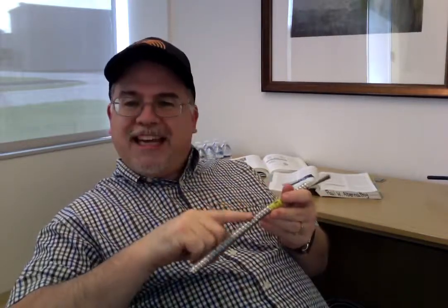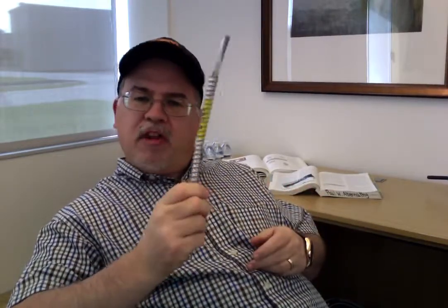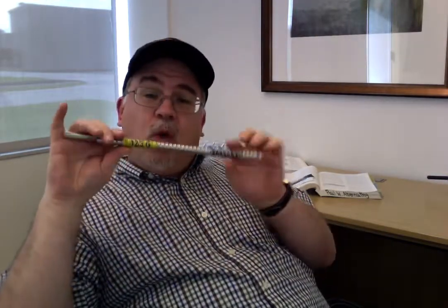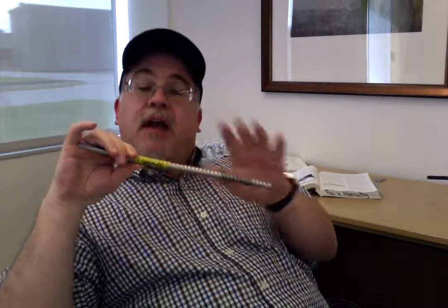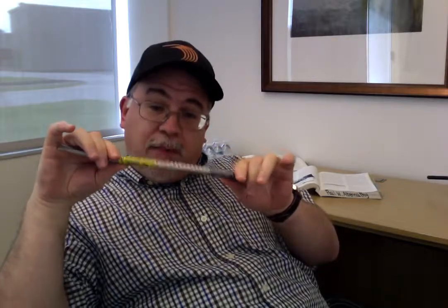More specifically, 250.118, which gives us the definition, if you will, of what an equipment grounding conductor can be. Well, this armor cannot be, because the code doesn't provide for it. That is why we have to put the equipment grounding conductor in it. Now, let's say we want to use this armor of an MC cable as an equipment ground and as an effective ground fault current path.